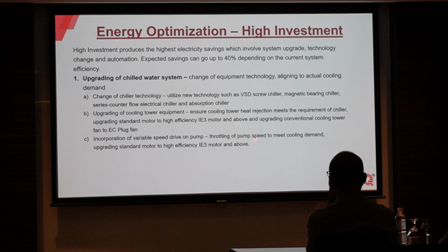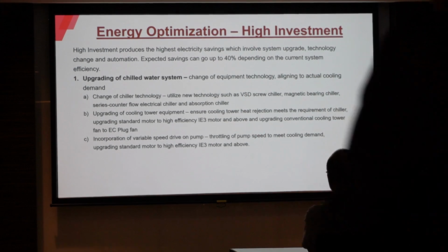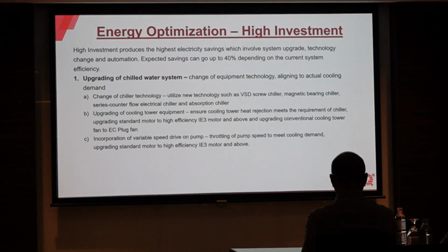This VSD screw chiller and magnetic bearing chiller work best at part load. So if you install this to 100%, as long as you are operating anything less than 100%, the efficiency is very good. And then upgrading of cooling tower equipment. The cooling tower is considered one of the cheaper equipment in the chill water system. So if you really want to improve the efficiency of your chill water system, oversize your cooling tower. Because as long as your heat rejection is efficient, your chiller will be able to operate efficiently.